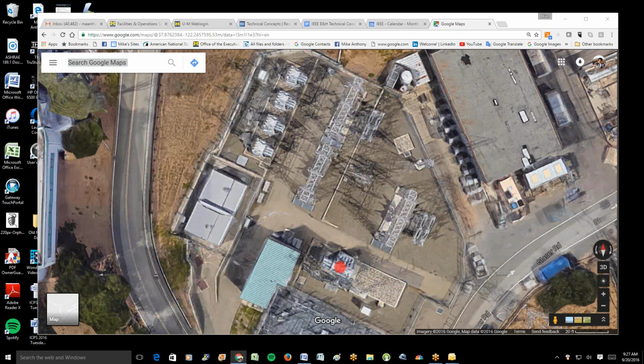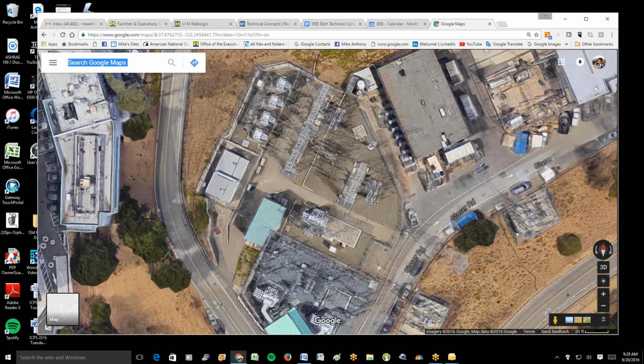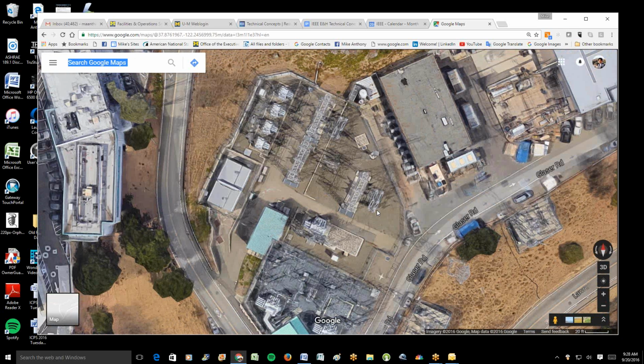We just completed yesterday a 4-week maintenance on that 115 kV yard. Prior to this maintenance, we were always able to move our load over to UC Berkeley on those two 1247 tie lines we have between us and their Hillside substation. But since our load has increased, and because of some configuration issues Jerry's having on campus, we couldn't do that this time. So this is the first time in probably 15 years that we've had to do maintenance in there while leaving one side energized and the other side de-energized, which created some safety issues for us with having lifts and workers up on the towers testing and cleaning insulators and open air switches. We just completed that maintenance, and we try to do that maintenance every 3 years on our system.